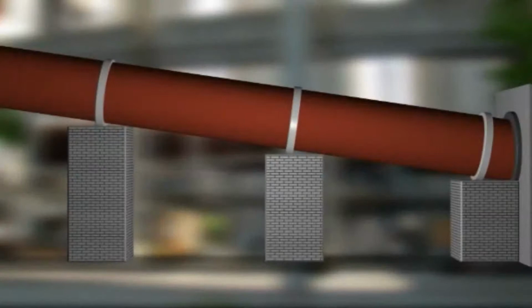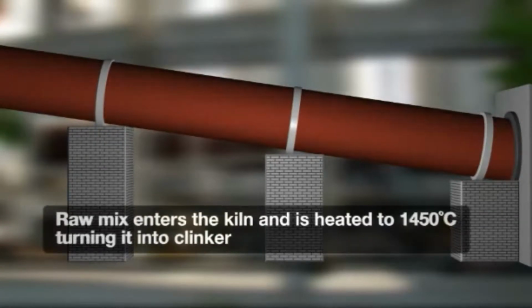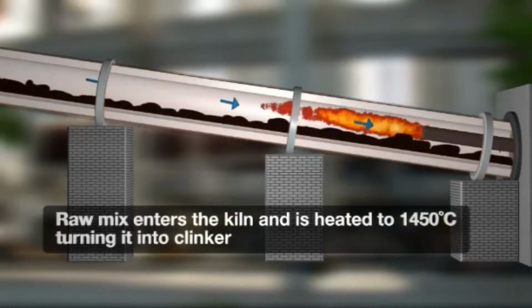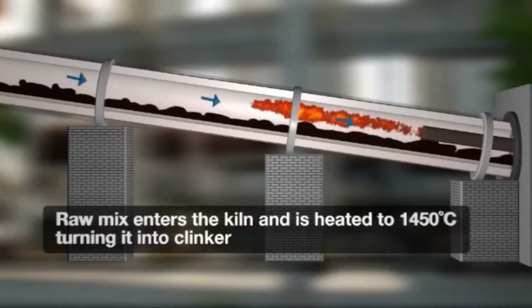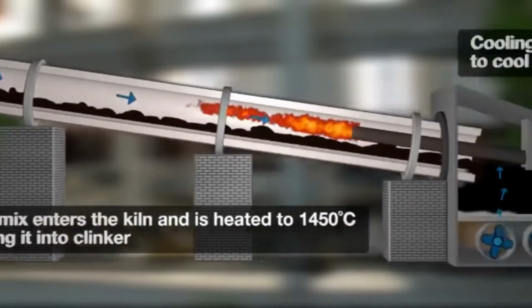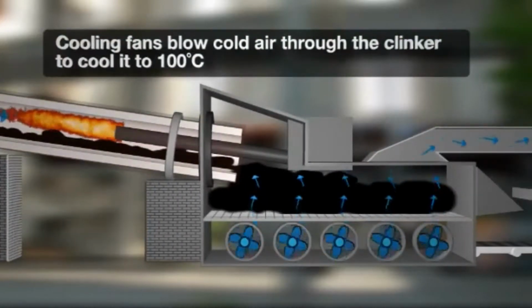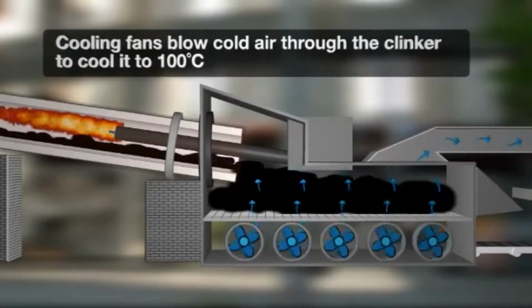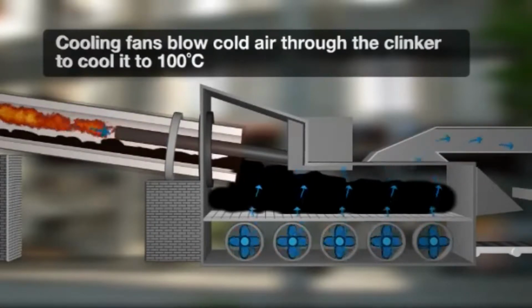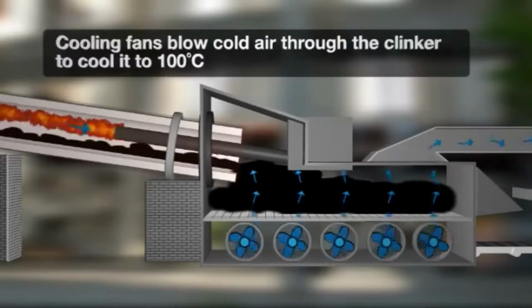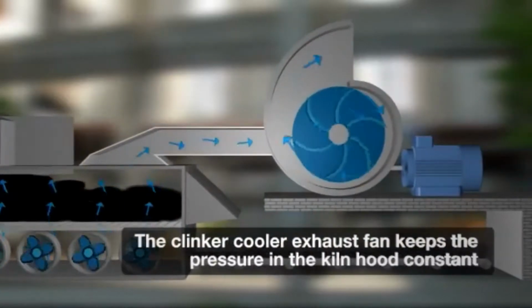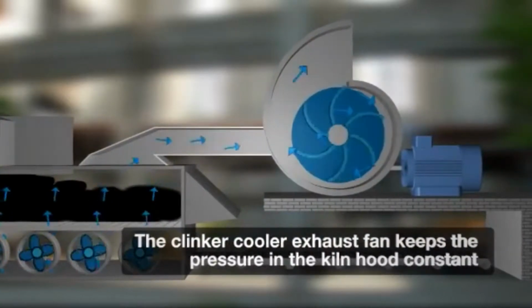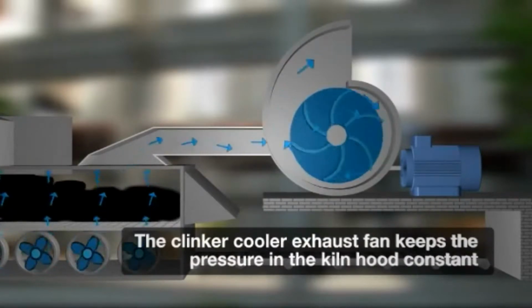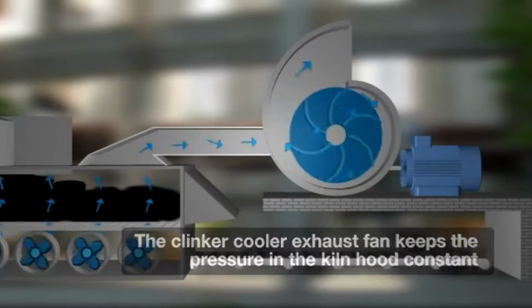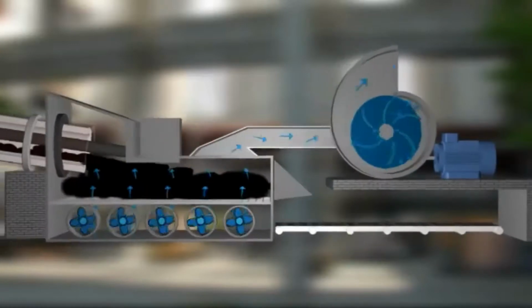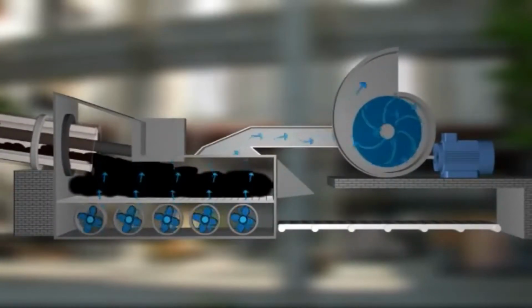Raw mix enters the kiln and is heated to 1450 degrees Celsius, where it is transformed to clinker. Upon exiting the kiln, the clinker is cooled to 100 degrees Celsius by way of the cooling fans, which blow cooling air through the clinker. By controlling the clinker cooler exhaust fan, the drive keeps the pressure in the kiln hood constant. It does this by regulating the fan speed that draws cold air through the clinker cooler in relation to the hot air that is being drawn through the kiln.